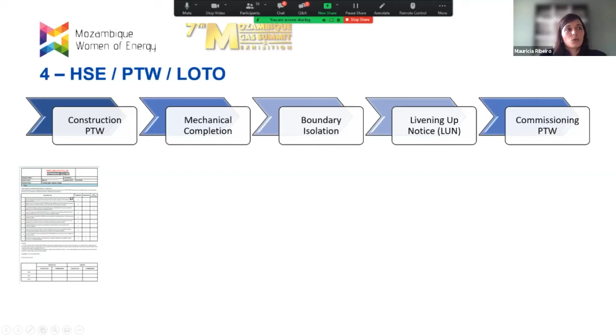Once you have reached mechanical completion, with construction and commissioning signing on the certificate, we check if there is any subsystem close to the one just about to be commissioned that is still under construction. Meaning if the subsystem we want to work on has construction people working nearby, we need to make a proper boundary isolation. In case we have a leak of energy, meaning power, fluid, heat, or whatever, we want to be sure we can isolate it from construction people so everybody can work safely on both sides. That's the idea behind this.